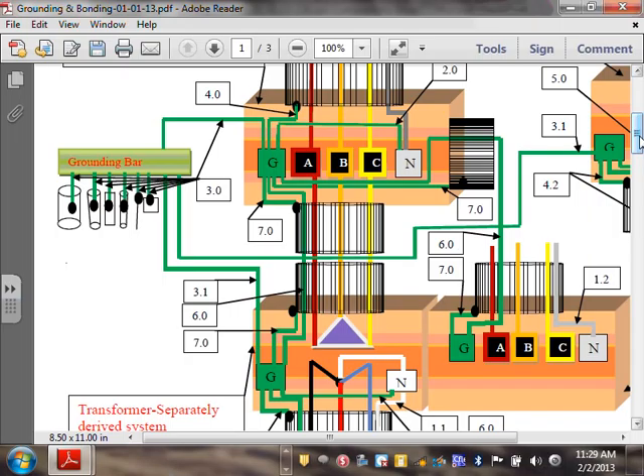So you will almost always end up with an equipment ground conductor on both sides. Put a junction box in between there. You have to put the bonding bushings and bond everything. Yeah, you have to use bonding bushings now. The challenge. Okay, so we know we have to pull an equipment ground conductor because of what we are almost always using. Do you guys bring rigid to a transformer? You typically use flexible metallic conduit for vibration, and you pull an equipment ground conductor.